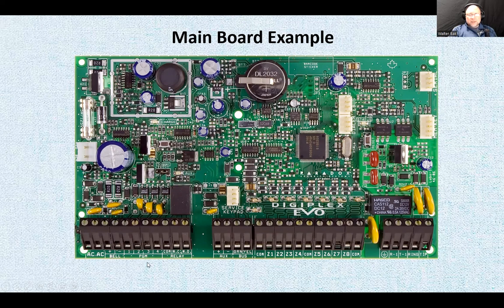They work differently with different security systems, so you've got to consult the manual or sometimes technical support. Basically, those turn on, and usually like this one here, once activated, it will connect to ground. So 1, 2, 3, 4. Normally they will be floating, but different systems will have different configurations of those. So if you have some other thing connected to, let's say, the plus terminal of the auxiliary input or the auxiliary output, then the other terminal of whatever device you have connected to the program, if the program is activated, is going to connect that to the ground. So you're going to have from the plus through the device to the ground. So it's just activating different types of devices based on whatever conditions you want to choose. Here's the common terminal. So common, they're all common. It's just to complete the circuit for the zones.